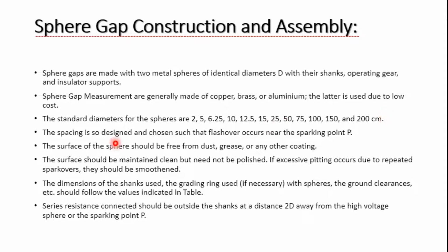The gap is designed in such a manner that flashover occurs near the sparking point P, which is the tip of the standard spheres. The surface of the sphere should be free from dust, grease and any other coating.